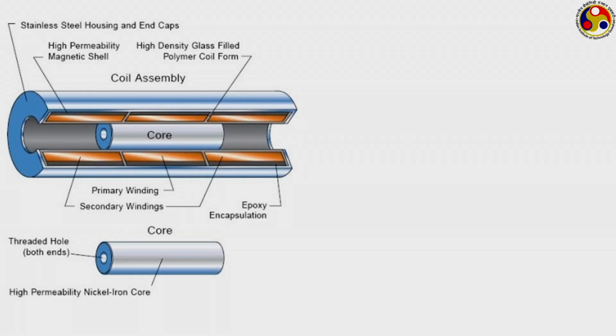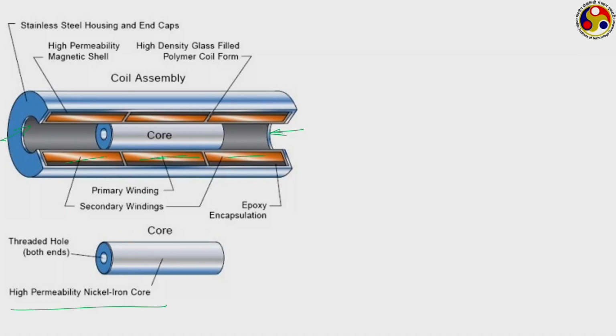This is a typical configuration. We have the core, generally made of highly permeable material like nickel iron, with a threaded hole through its center. On one side of the core we have the primary winding, and on either side the two secondary windings. They are encapsulated inside a particular medium, and generally both ends are left open, so that in an extreme situation, if subjected to a displacement beyond its limit, the core will just move outside the shell, preventing any kind of damage. This is the simple construction of an LVDT transformer.